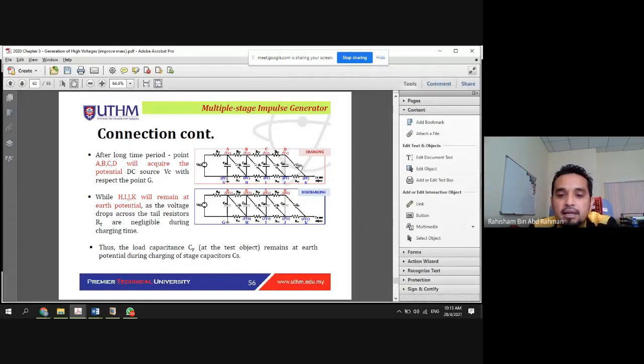Actually, we trigger it externally, or it can be manual, by the breakdown between the electrodes. In many cases, we just use external triggering because these trigger gaps need to be discharged at the same time. In order for us to have the desired magnitude level, we need to discharge this circuit at the same time. Okay, 1, 2, 3, 4, all of these trigger gaps need to be triggered at the same time. This is again the problem which I explained before.